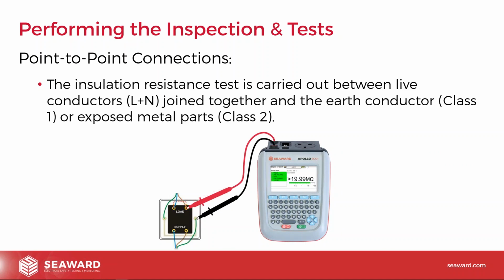Insulation resistance, again, generally we can do the insulation resistance test on class 1 and class 2 equipment. With class 1 equipment, it's done between the earth terminal and the line and neutral joined together, and with class 2 it's done between the line and neutral joined together and exposed parts. So exactly the same as we do a normal test on equipment, but in this case it's just using the point-to-point connections.